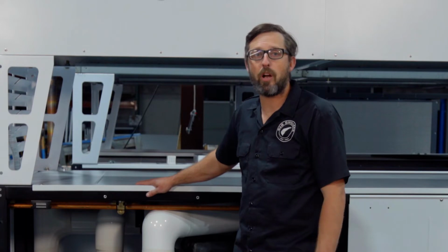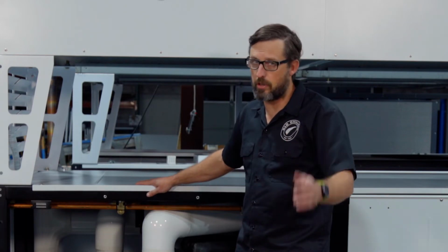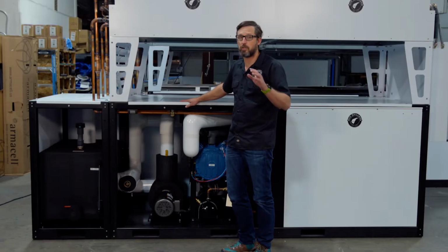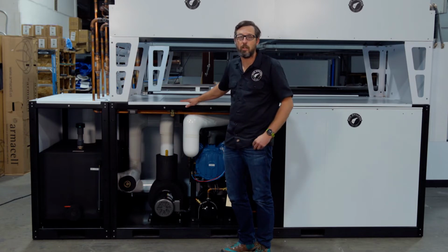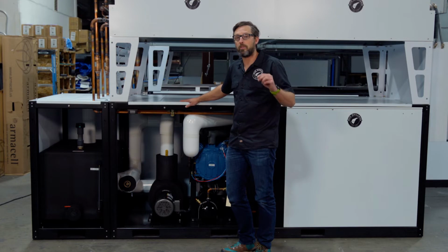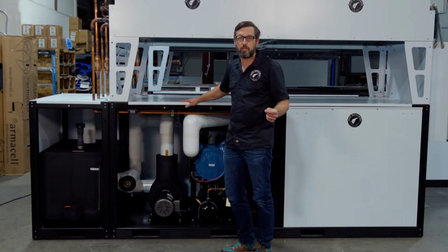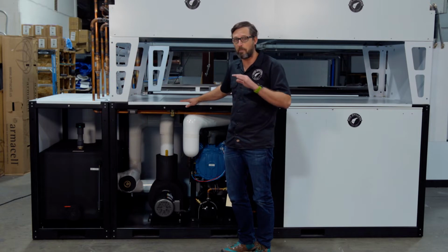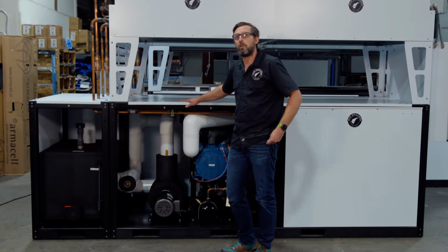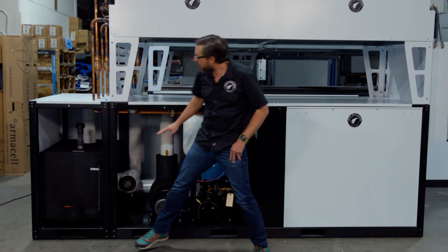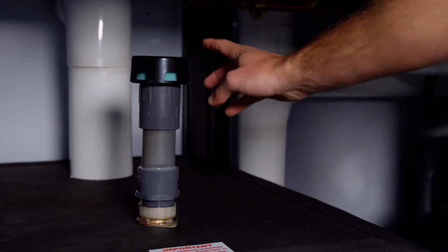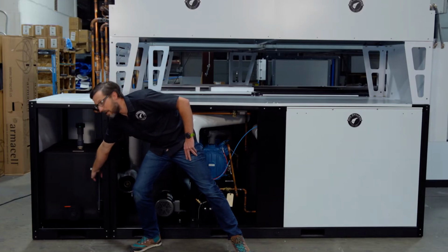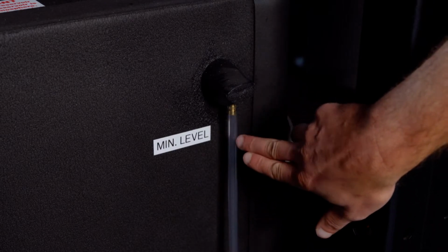Alright, so at this point we've gone through all the installation processes shown in the installation video, one of which was to ensure that all of the piping has been flushed and then very well dried. I'm going to go ahead and reiterate that here because once again, most of the problems that we see with these units is with lean Dynalene, meaning that water has been introduced to the system. So we want that piping to be extremely dry. Once we've ensured that, we're going to go ahead and add Dynalene to the reservoir itself. You can see that there's a minimum level. We're going to want the Dynalene level above that.